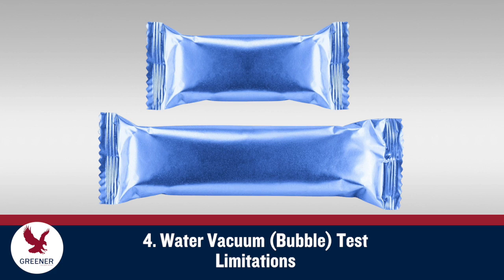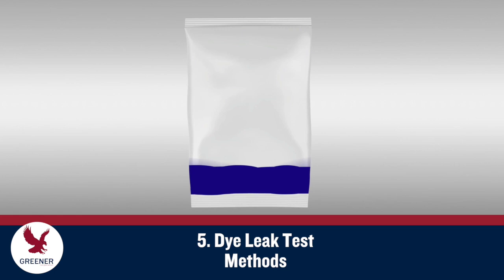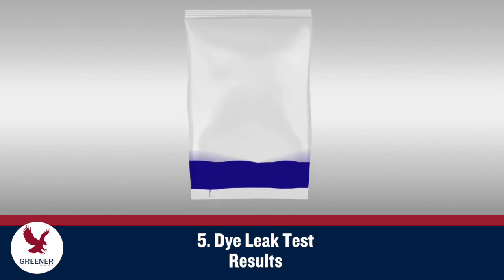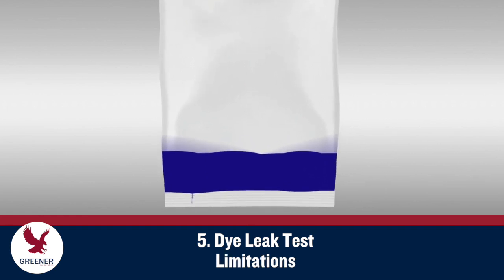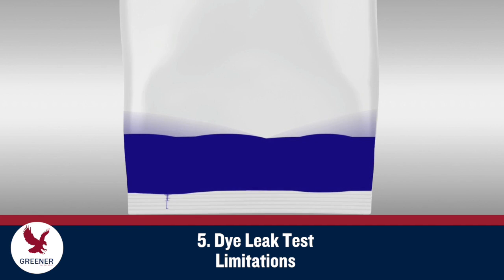Water vacuum tests don't accurately measure leak size, since results are influenced by the initial air fill, size, and geometry of the package. Initial air fill must also be considered when assessing the impact of pressure changes during shipment. Since the manual squeeze test is not accurately repeatable, results can be inconsistent. Dye leak tests can also indicate the presence and location of leaks. Colored dye is injected into the package, held for a set time with the seal oriented horizontally at the bottom, and then inspected. Leaks are indicated by places where the dye has migrated through the seal. The dye leak test tends to be less sensitive for smaller leaks and doesn't quantify the magnitude of leaks.